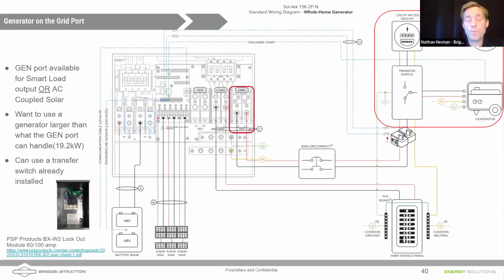Now, if we have a microinverter array, we might also want to have a generator. Let's just look at a simple example of using a generator with a Sol-Ark. We can use a generator on the gen port of a Solarc if we don't have AC coupled solar, but we could also use a generator on the grid port. Daniel and I often prefer this method of installing generators using the grid port. Certainly for off-grid, they even recommend this. But we prefer this because it leaves the generator port open either for AC coupled solar or for smart loads. Additionally, you're no longer limited to the 80 amps of continuous AC power of the gen port. You can have 200 amps from your generator.